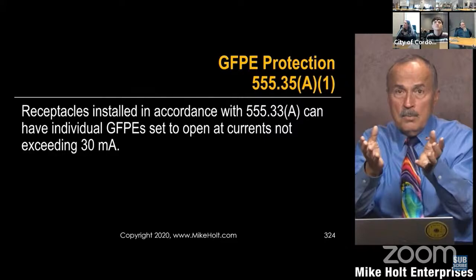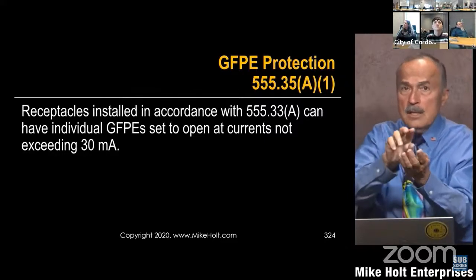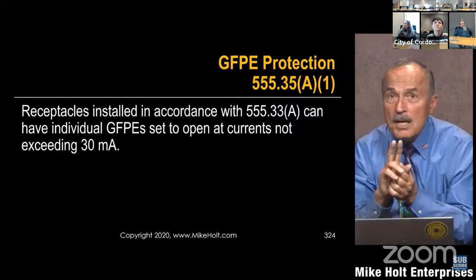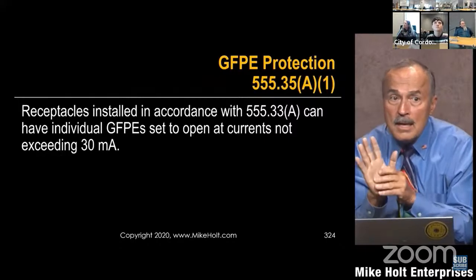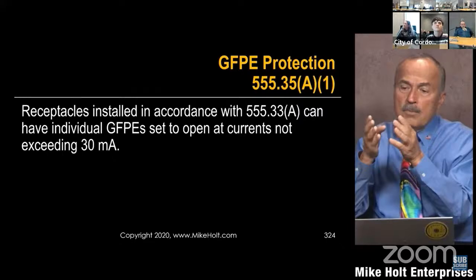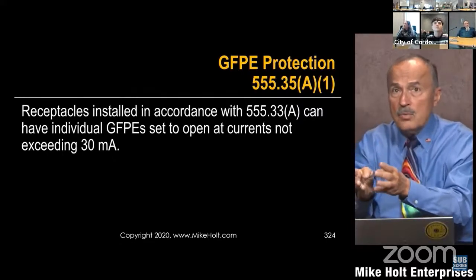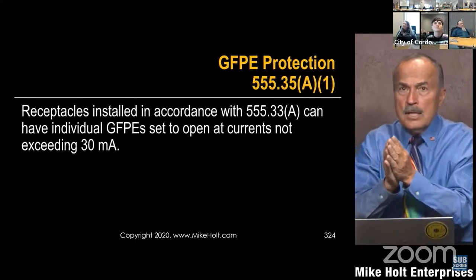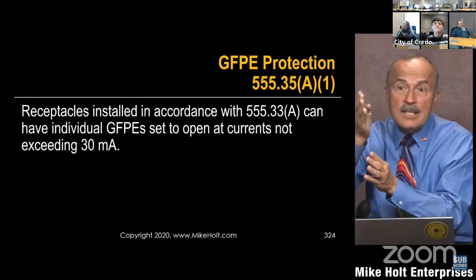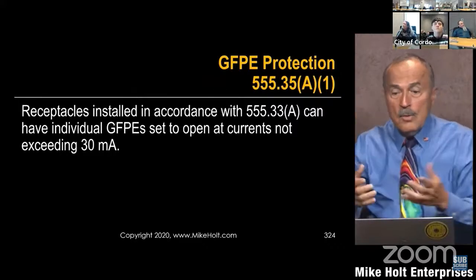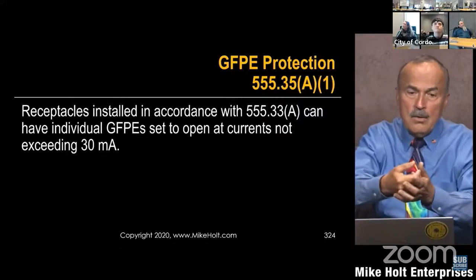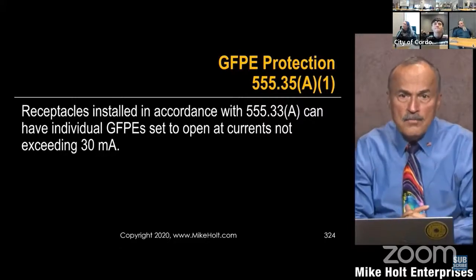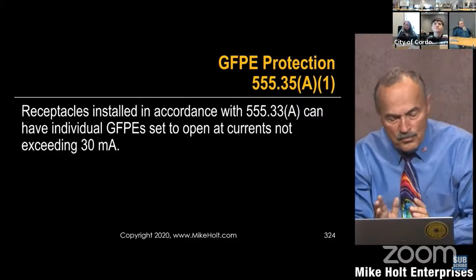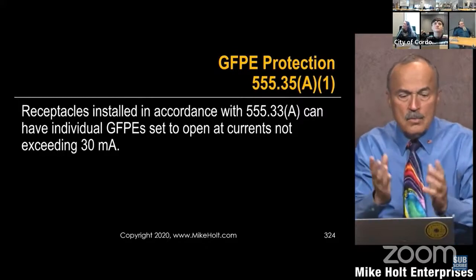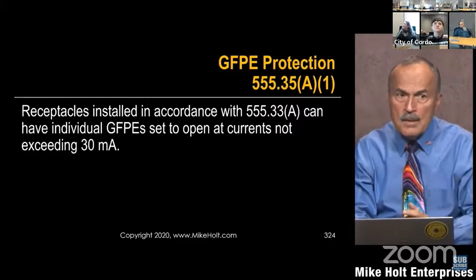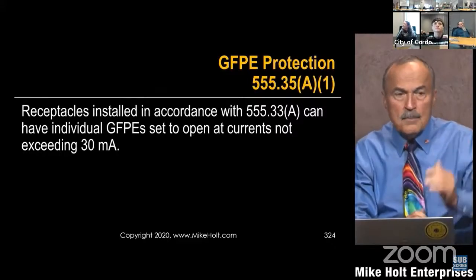And then, okay, well, the 50 amp receptacle has a 50 amp breaker, but that breaker is going to be a ground fault protector set at 30 milliamperes. And then the 20 amp, 125 volt receptacle is being supplied by a GFCI set at 5 milliamperes. So when I get my boat and I plug it into shore power, I'm having 30 milliamperes of ground fault protection of equipment. It can't be 5 milliamperes, can't be GFCI, because it more than likely won't hold. So 30 milliamperes is going to be the maximum level that you can set that protection.